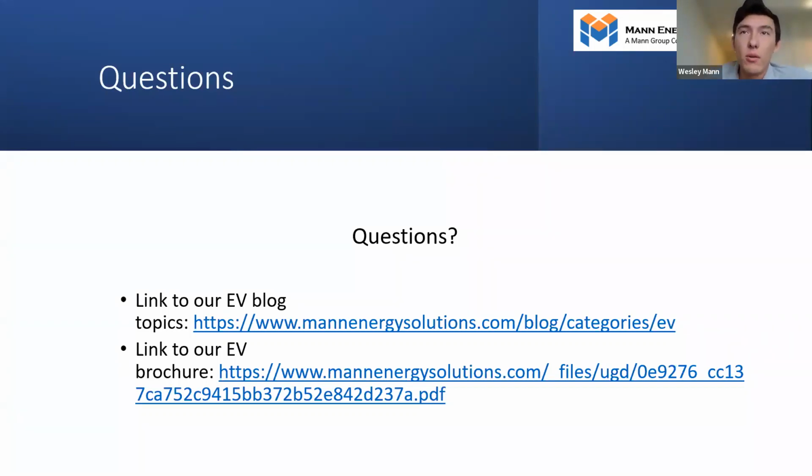Yeah, very good question. So when we're talking about individual tenants, the solution we generally recommend is the central panel controller, what I was mentioning in my presentation. It can give the control directly to the building owners or property management, because all this central controller is doing is that it's hardwired to each of the individual chargers, and it's metering them. So this metering data is available to the building, so they can bill directly to the tenants.